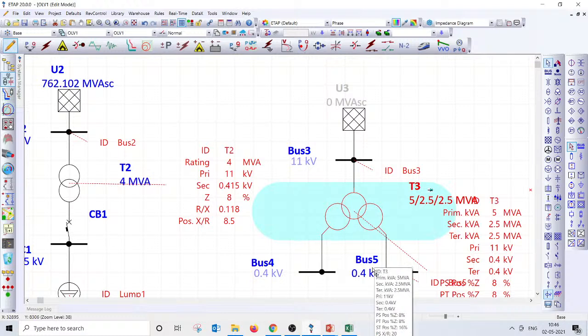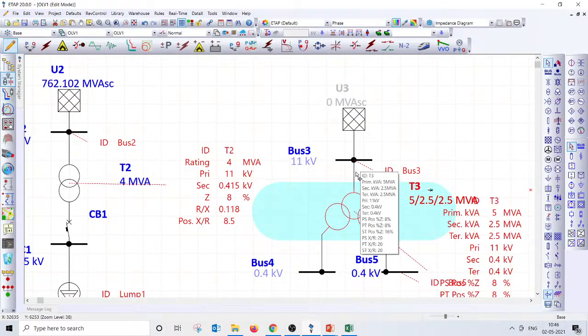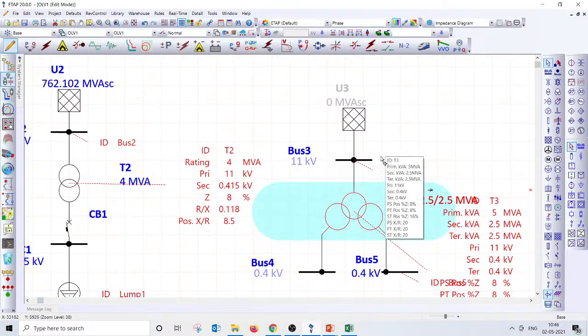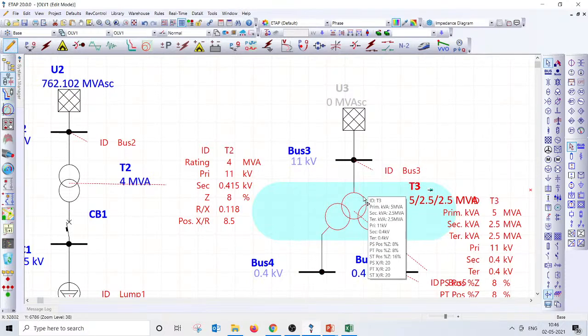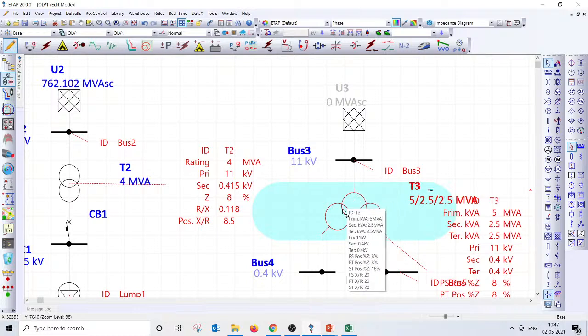you will have an LV circuit breaker in the switchgear as an incomer, and you will have CTs, relays and circuit breakers in the medium voltage. If there is a fault anywhere in between, your breaker has to trip and isolate it, otherwise your transformer will get damaged. So it's pretty straightforward. If there is a fault in any one winding, whether 11 kV or 415 volt, or even in this cable, which I have not really modeled but you can put it in the model, because you always connect this transformer through a cable to the switchgear. When there is a fault in this cable or that cable, it has to be isolated.